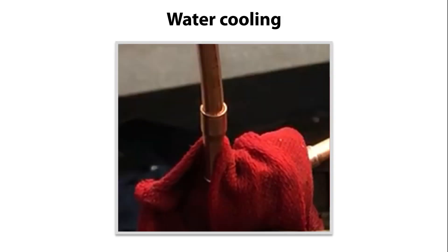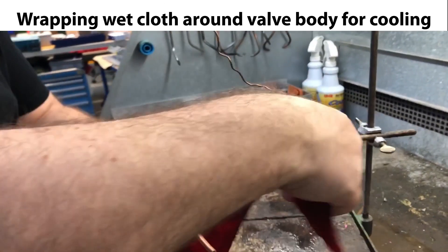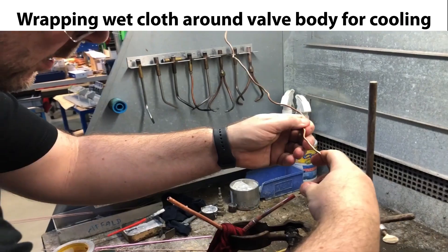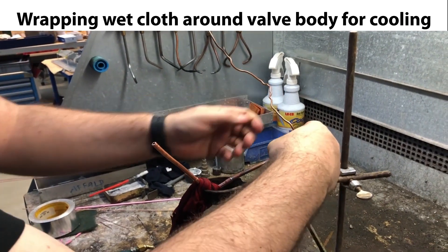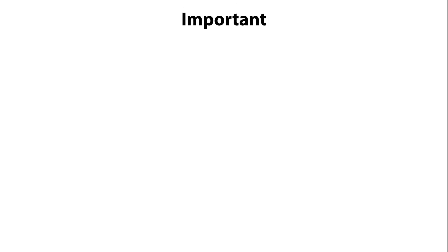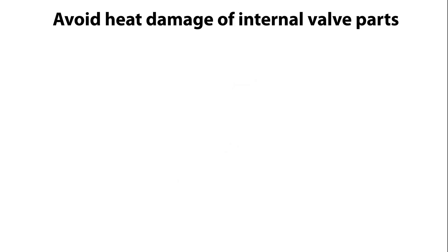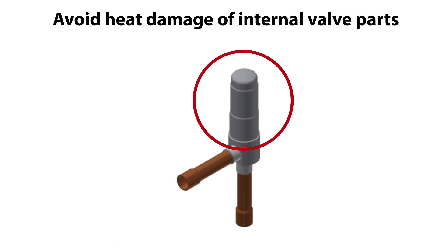Another very important step is water cooling of the valve during brazing. This is done by wrapping a wetted cloth around the valve body as seen here, and then wetting it with sufficient cold water to keep the valve body cooled down during brazing. This is important to ensure that the internal valve parts are not heat damaged by the brazing heat.